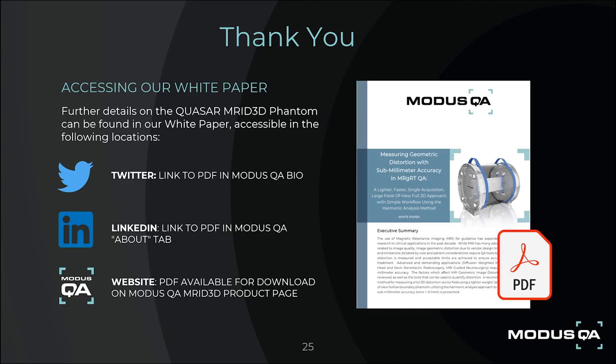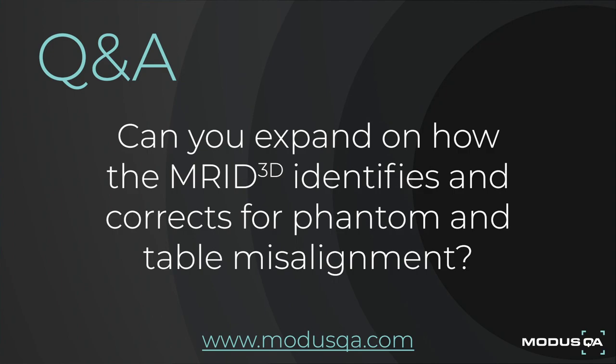Thank you so much, Enzo, for your great presentation. The first question is: can you expand more on how the MRID 3D identifies and corrects for phantom and table misalignment? Is it just the markings on the outside of the phantom? There are several design elements within the phantom that are used for correcting for any misalignments. The phantom has a series of fiducials on the boundary, and we have contrastive boundaries at selected points to act as landmarks for the software to correctly register with the phantom.